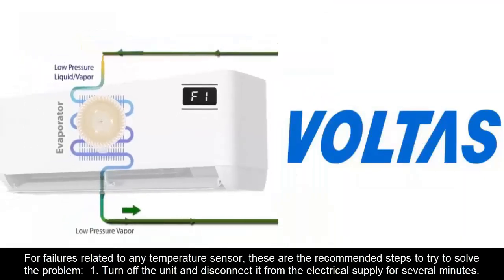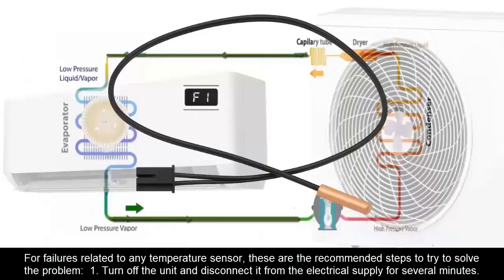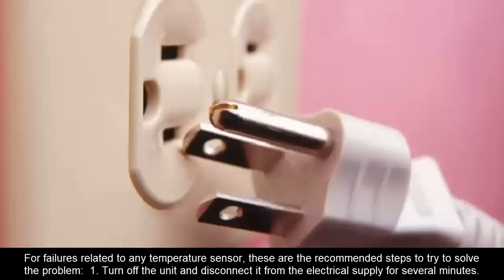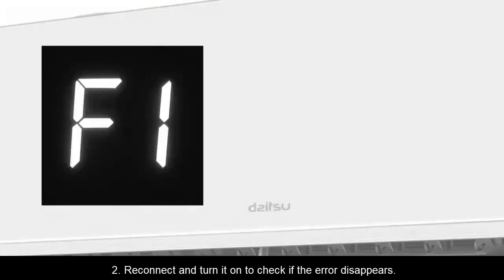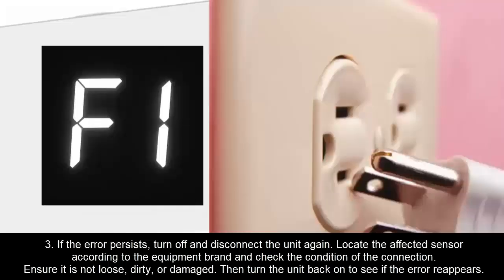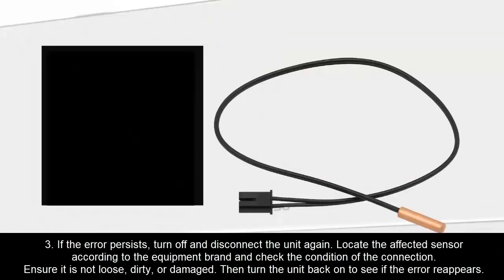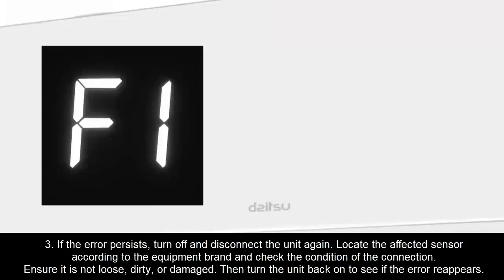For failures related to any temperature sensor, these are the recommended steps to try to solve the problem. 1. Turn off the unit and disconnect it from the electrical supply for several minutes. 2. Reconnect and turn it on to check if the error disappears. 3. If the error persists, turn off and disconnect the unit again. Locate the affected sensor according to the equipment brand and check the condition of the connection. Ensure it is not loose, dirty, or damaged. Then turn the unit back on to see if the error reappears.